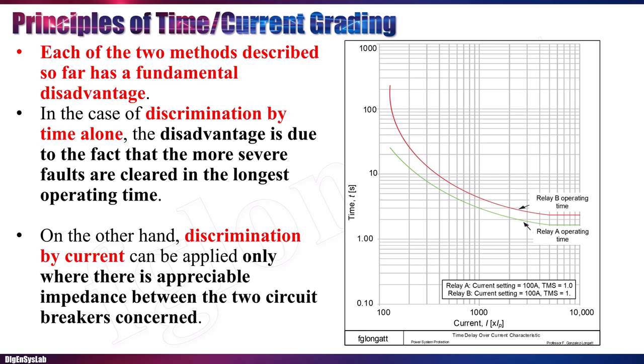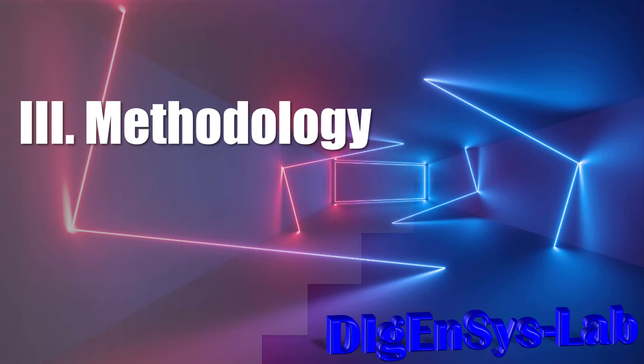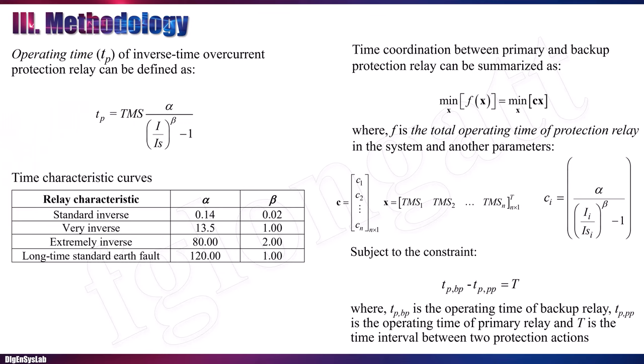Using different curves and a separation between curves based on current and time, this is basically the scheme for grading and setting the non-directional overcurrent relays followed in this paper. Now let me describe the methodology. When using inverse time overcurrent protection relays, there are standards that define the operating time characteristic.